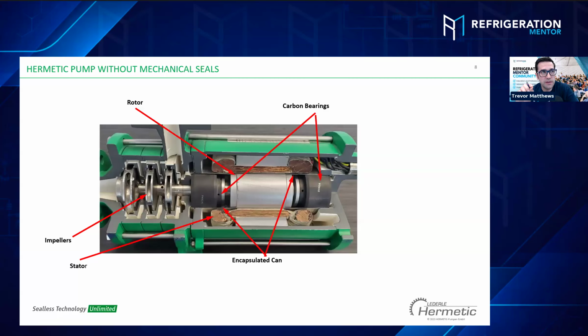So the bearings could be damaged by cavitation or pressure differential, and then as a technician, I can actually pull this apart and change the bearings if the motor's still good, and get that pump up and running without having to get a new pump. Is that correct? Yeah, exactly. It's correct. Awesome. That's amazing. Or replace the impellers, basically. Yeah, it's only just replace the bearings and the gaskets. It's very simple to maintain this pump.